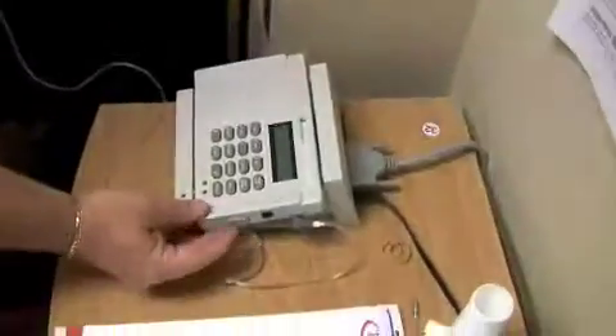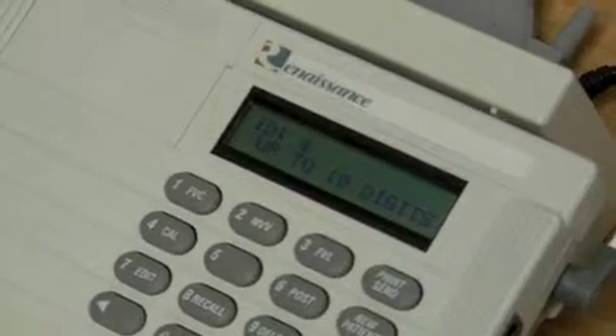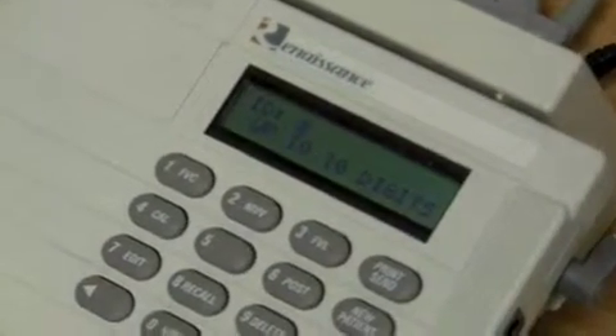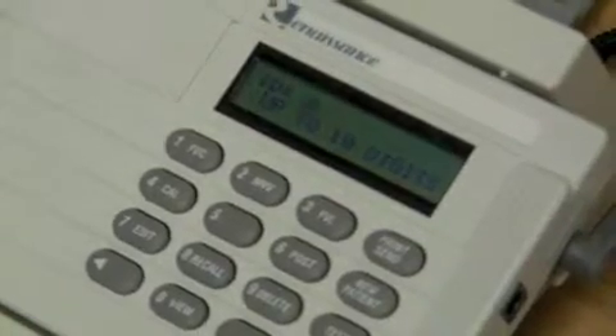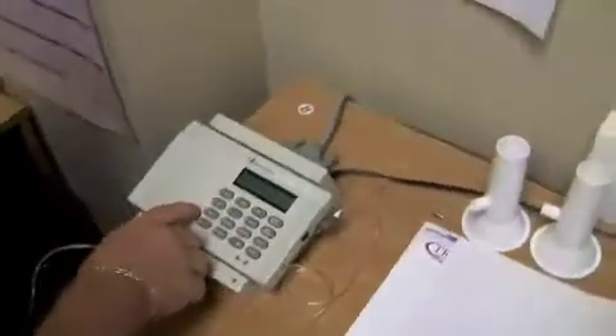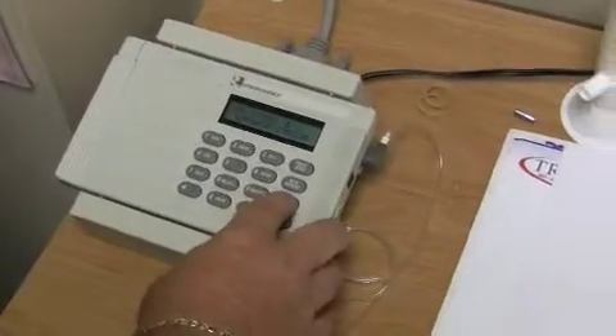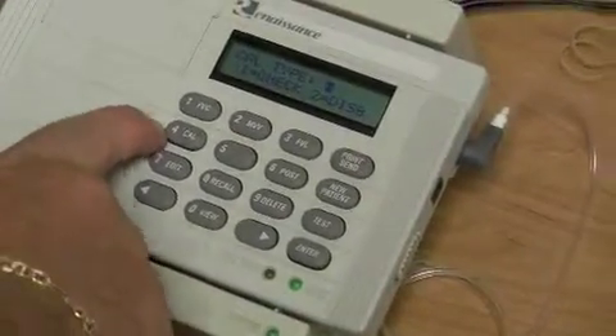The first thing that we're going to do, of course, is flip the switch on. We're going to turn on the calibration base unit. The first thing you're going to notice is the last time the calibration check was done on this machine was on 10/7, which tells me the last spirometer test must have been done on 10/7. When you see the ID flashing, you want to hit the 4, the CAL for calibration. We're going to push the test button and the calibration, which is 4, and it's automatically going to bring up CAL type. It's going to be a 1, so you push the 1 and you hit enter.